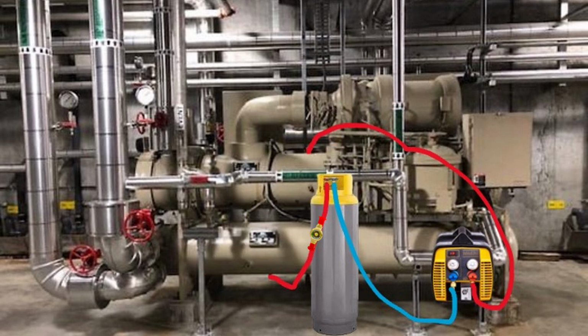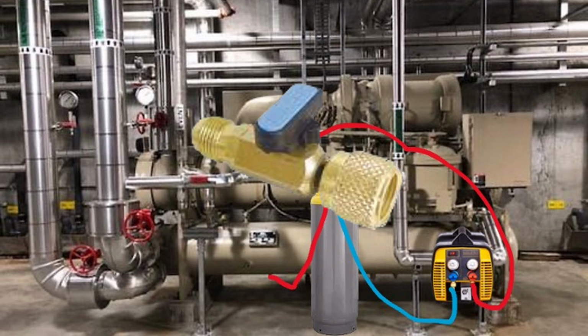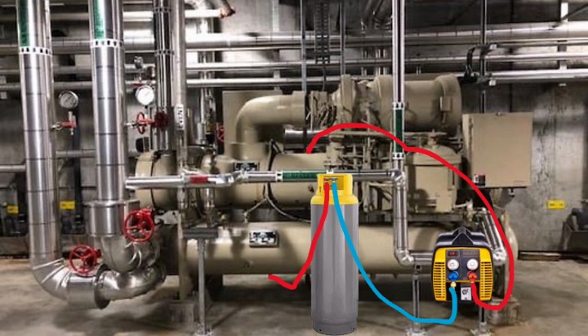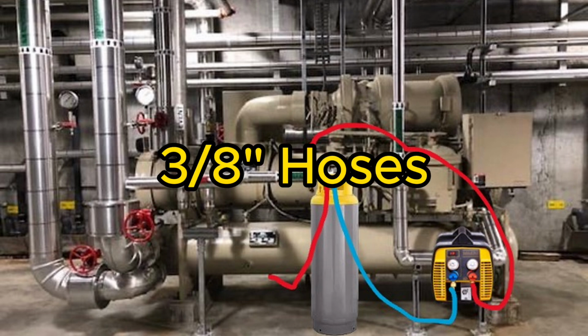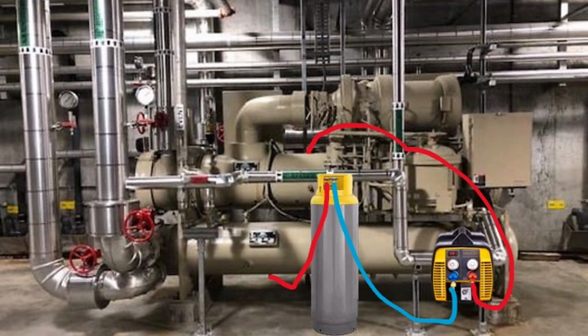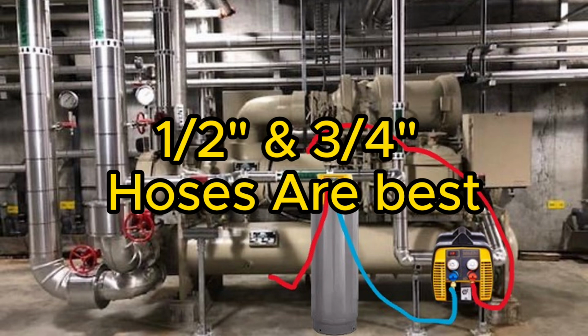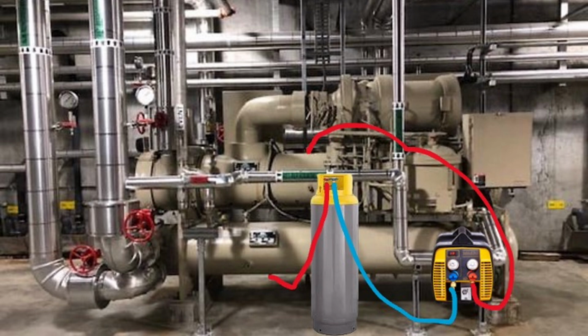A quick tip: if you are switching between many tanks, the use of refrigerant ball valves will make it easy to swap your hoses around and switch between tanks without losing any refrigerant. You should also use a minimum of 3/8-inch hoses when recovering large amounts of refrigerant. 1/2-inch and 3/4-inch hoses are ideal if you are doing this regularly.